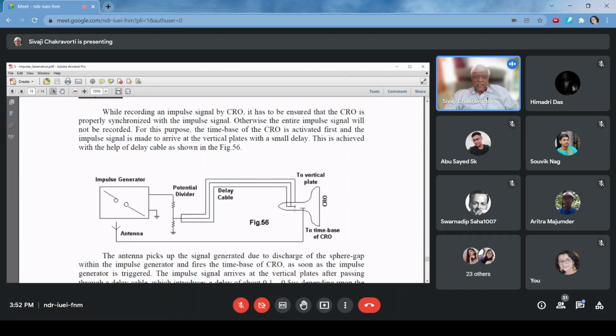Otherwise you can't record, or you will miss some part of the initial part of the y-axis quantity. For a lightning impulse, if you miss that, almost half of the wave is gone, because the wave front is only 1 microsecond. So even missing 0.5 microsecond means half the signal is gone. This cannot be done simply. So what do we do?